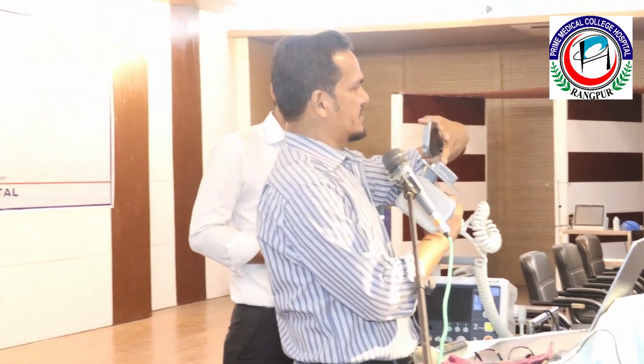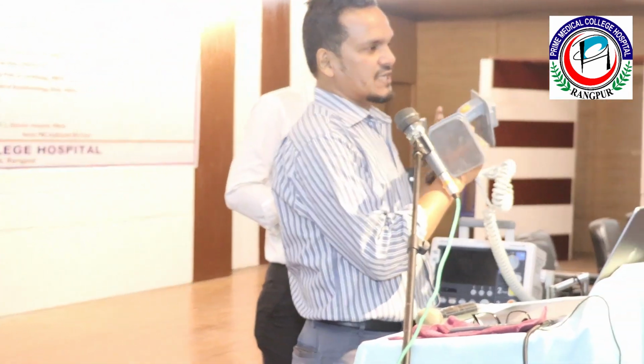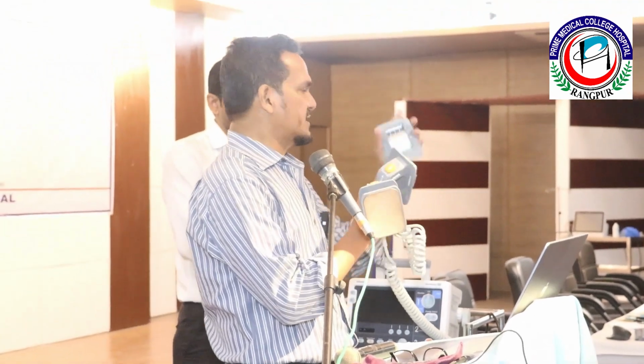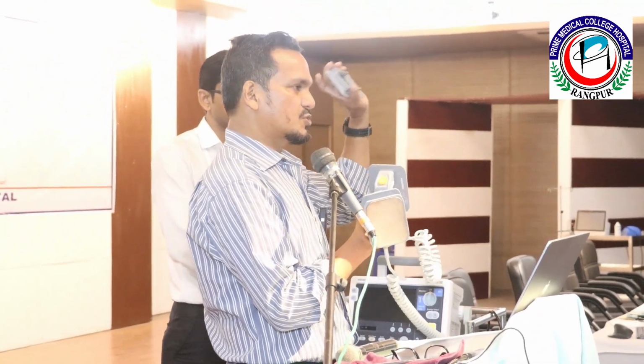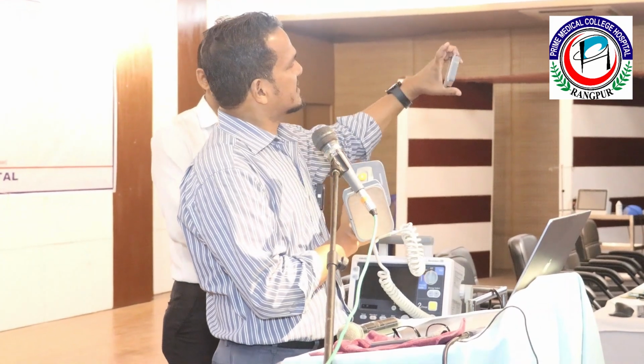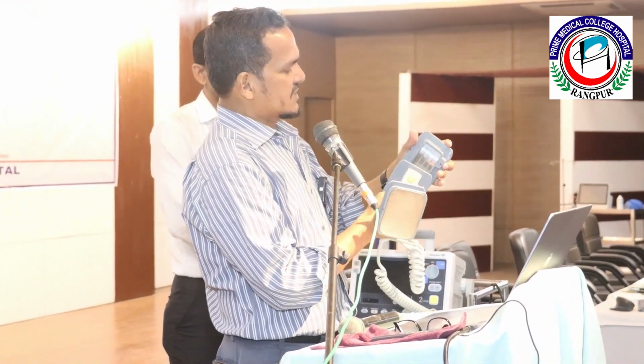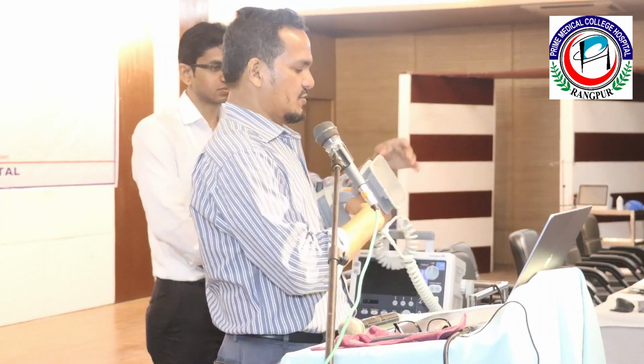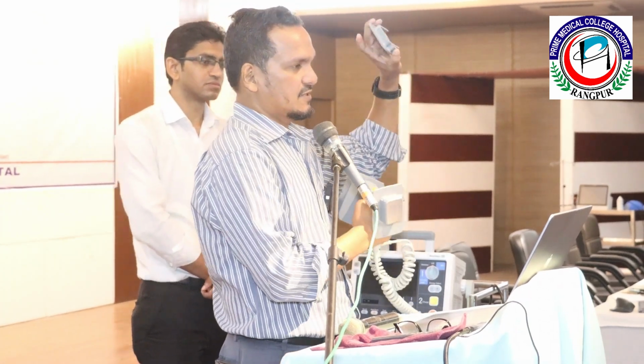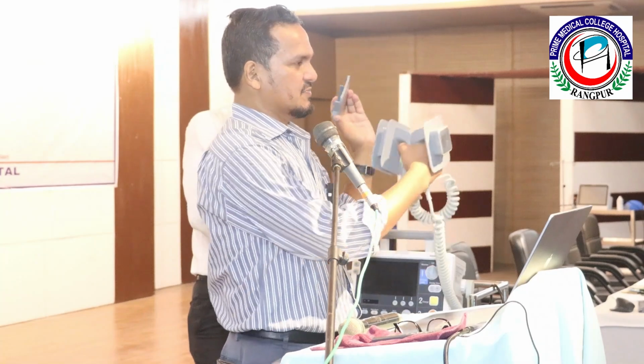This is the pediatric paddle. The chest wall is smaller, so the shock delivery surface area is smaller, and it is inbuilt, 2-in-1. Just press the button, slide it, and now it is adult. Both can be removed. This is the adult, this is the pediatric paddle.